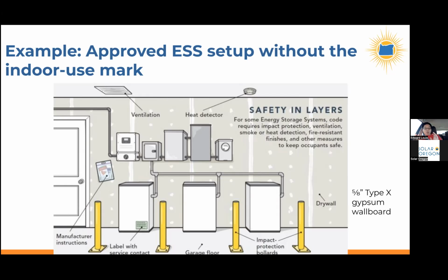And you're also required to drywall the walls and ceiling of the area that the battery is in. And you need to not use 1/2 inch drywall for the walls, but you need to use 5/8 inch drywall, which is a type X drywall that's typically used in ceilings, but you also have to use in the wall as well. And you also need to have some labels and emergency shutdown instructions within line of sight of the batteries. So those are some of the rules that NFPA 855 has implemented.